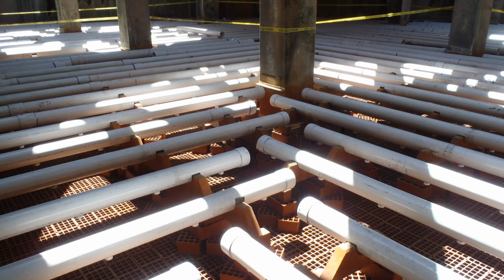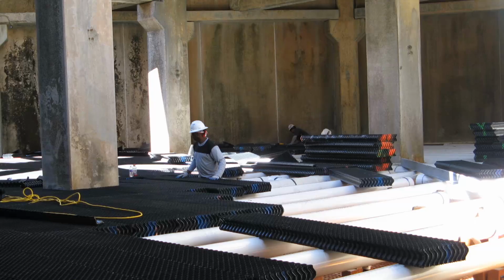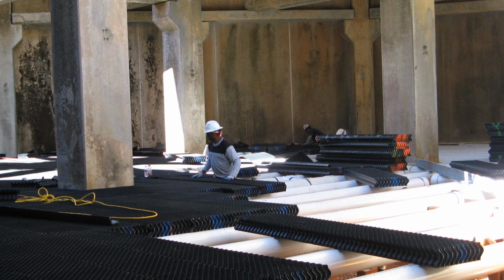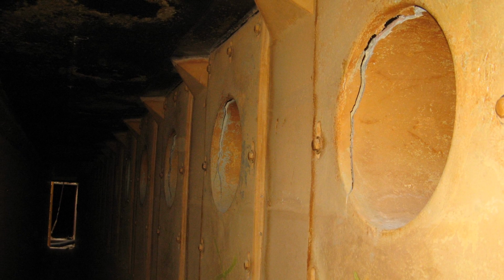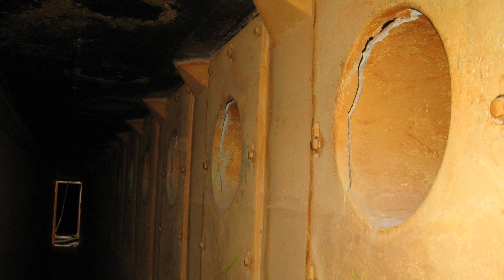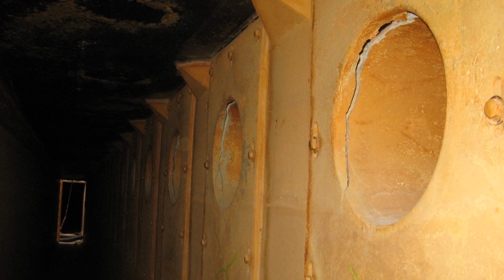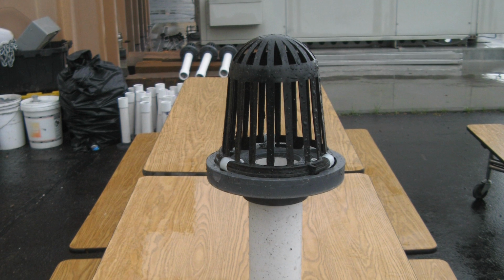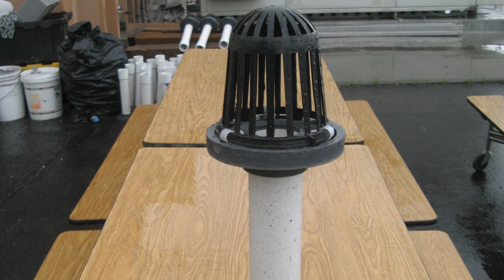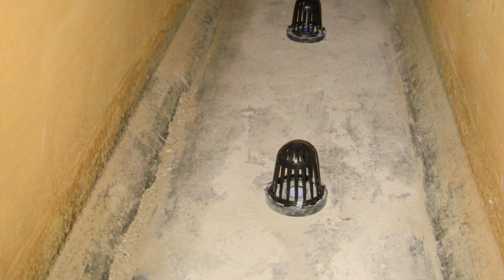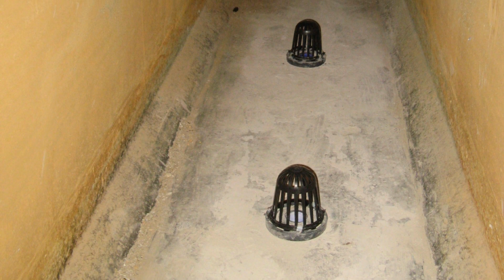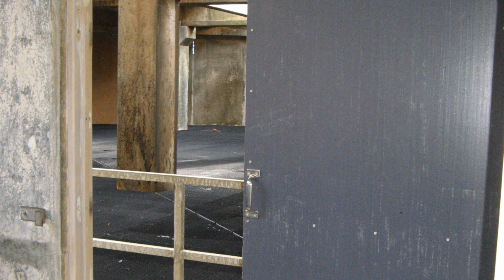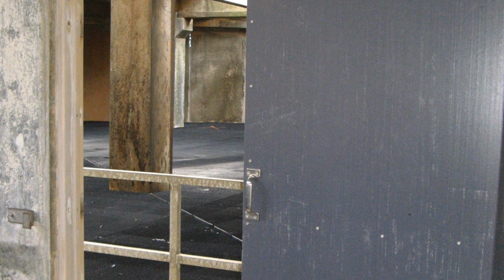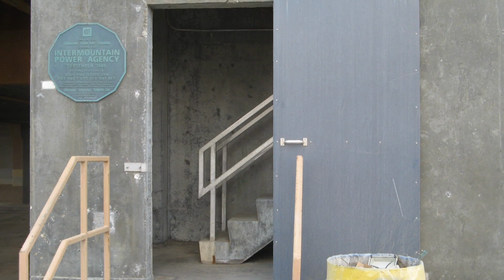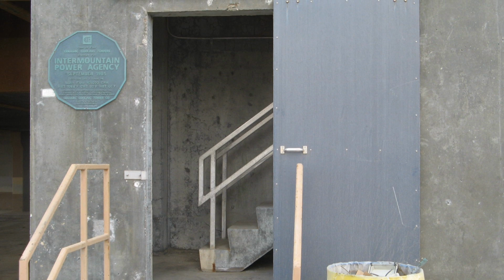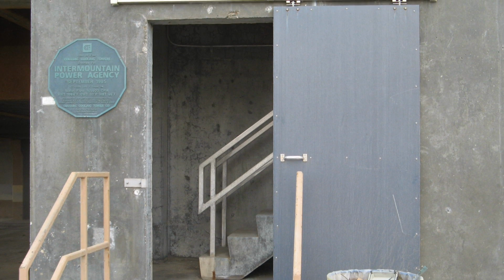In the cooling towers for both units, the lower PVC fill was removed and replaced. About 1/2 of the fiberglass flume plates, which were cracked or broken, were removed and replaced. Nozzles and strainer covers were added in the distribution flumes to expand water coverage over the lower fill, plus to reduce sediment loading in the flumes. New internal and external sliding doors were also replaced. The functionality of the interior doors has a large impact on performance whenever a cooling tower fan is taken out of service.